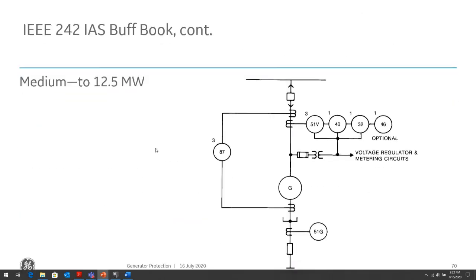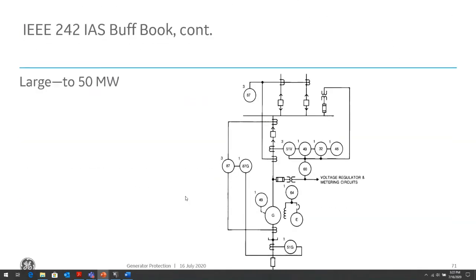When we go up from small to medium voltage generators, the additional protection could be an 87. The 87 will require additional CTs and additional relays, with a little more testing involved to commission. Then when we talk about larger generators, this is most of what we've discussed today. We talked about the 59, the 87 phase, the 87G, the 64 third harmonic differential, the third harmonic undervoltage, and the zero sequence overvoltage. All of those are covered within these guides.